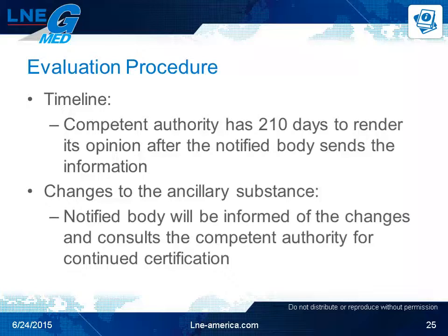The aim of this evaluation is to make sure that all documents needed are included in the file. According to the MedDev 2.13 Rev 3, competent authority has 210 days to render its opinion after the notified body sends the information. The clock of 210 starts only once the request has been judged eligible.